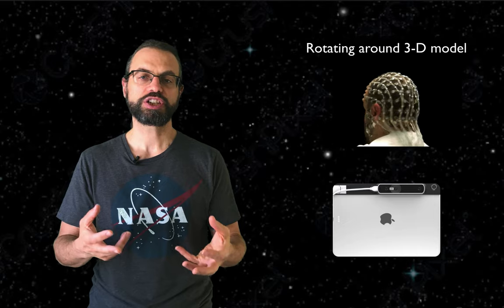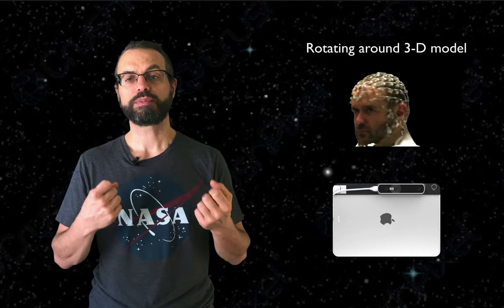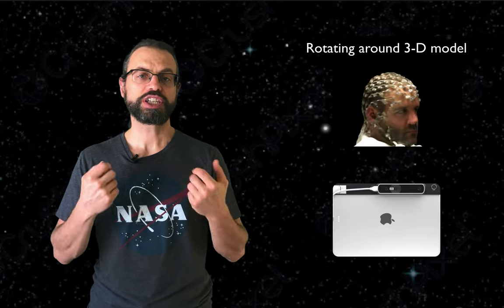The 11th advice is to scan your EEG electrode position and, when possible, collect anatomical MRIs for EEG source localization. Of course, first you want to select an EEG cap of the right size for the participant and position your EEG cap properly. Then scanning electrode is simpler than it sounds. You need an iPad Air equipped with a special 3D camera. Scanning takes about 30 seconds. Then all the software to extract electrode position from the 3D model is available open source. When you have the electrode position, you can perform better alignment between the caps of different individuals.